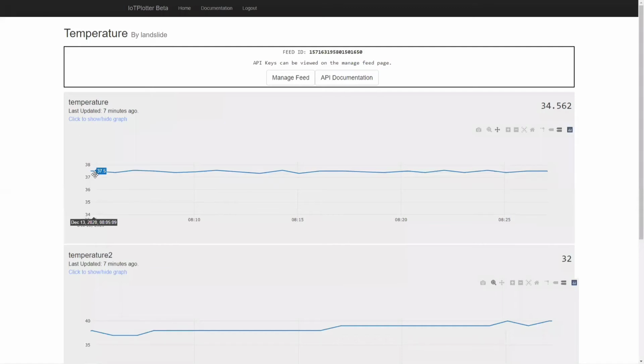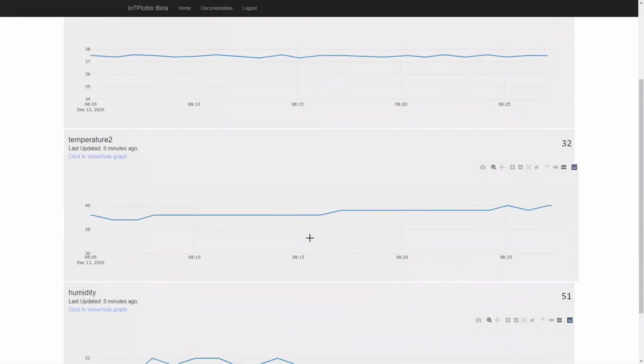This is the temperature from the digital thermometer. This is the one that we use to control the lamp. Here we can see that the temperature doesn't change much at all. It maintains the temperature at about 37.5. This is the temperature measured at the humidity sensor, which is also a temperature sensor. Here we can see that the temperature, which was about 37 or 38, did increase all the way to 40 degrees Celsius. So there's a gradient of temperature between these two.